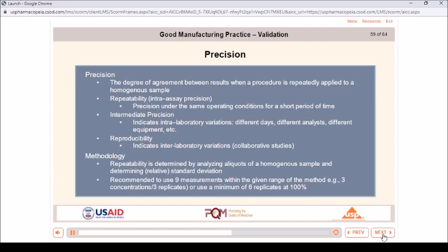Methodology. Repeatability is determined by analyzing aliquots of a homogeneous sample and determining relative standard deviation. It is recommended to use 9 measurements within the given range of the method, e.g., 3 concentrations with 3 replicates each, or use a minimum of 6 replicates at 100%.